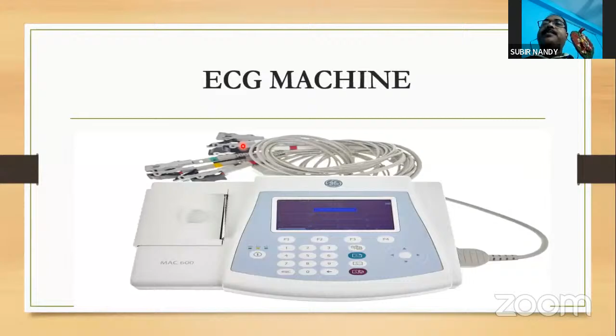ECG machine routine maintenance. The ECG machine should be regularly maintained to prolong the life of the ECG machine and its components. Specific requirements are as follows. Keep the electrodes clean after each day of ECG recording. If there is rust on the electrode made of copper alloy, the rust stain can be wiped off with fine sandpaper and then immersed in physiological saline overnight to form a stable film on the surface.